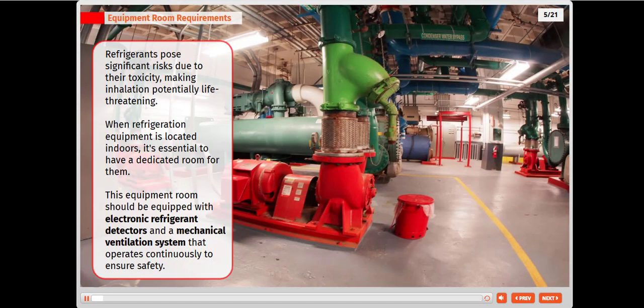Refrigerants pose significant risks due to their toxicity, making inhalation potentially life-threatening. When refrigeration equipment is located indoors, it's essential to have a dedicated room for it. This equipment room should be equipped with electronic refrigerant detectors and a mechanical ventilation system that operates continuously to ensure safety.